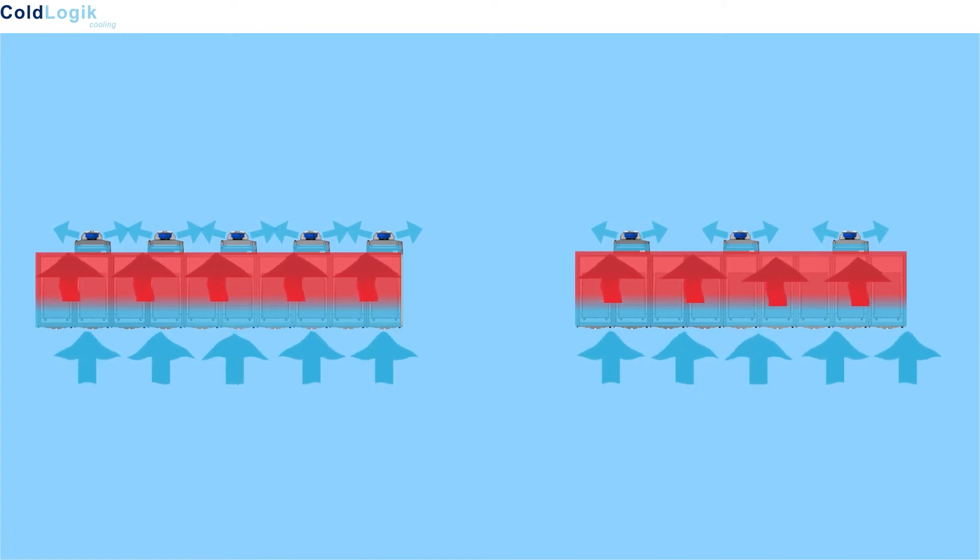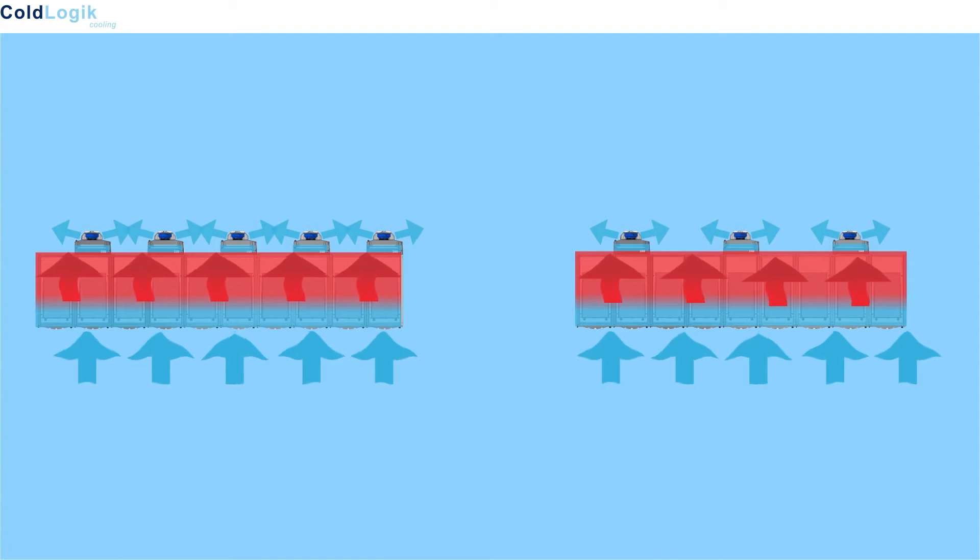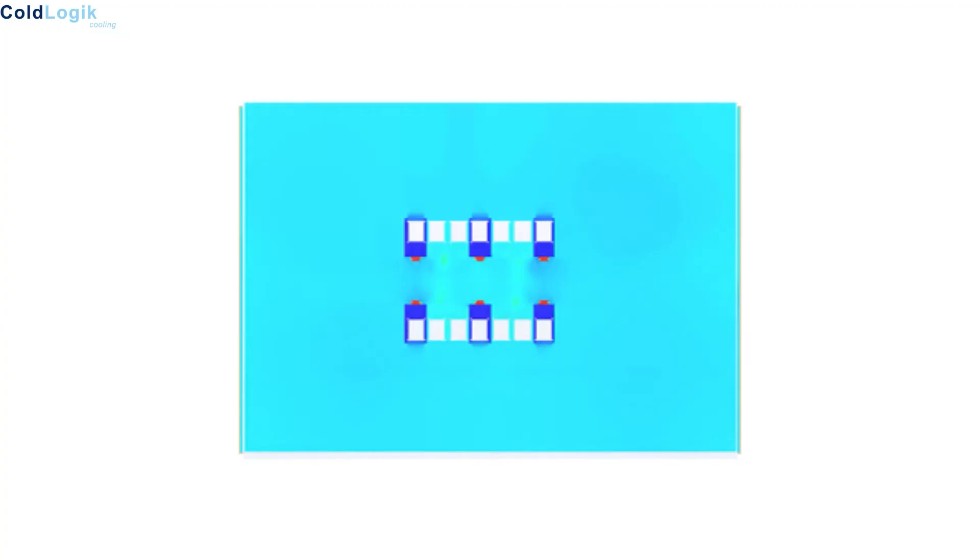Air temperature sensors linked to the ColdLogik Management System, or CMS, ensure that the correct air volume and temperature mixing with the warmer air coming off the adjacent racks meets the room's desired set point. By constantly monitoring and making minor adjustments, the overall room temperature is maintained to within plus or minus one or two degree Kelvin of the set point.